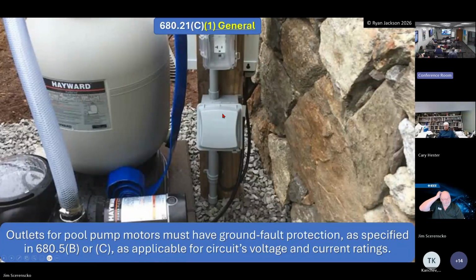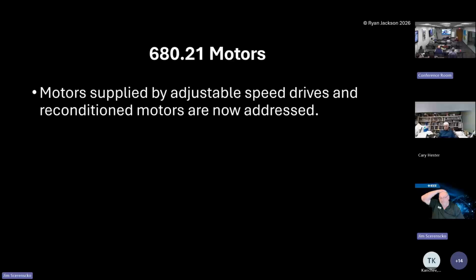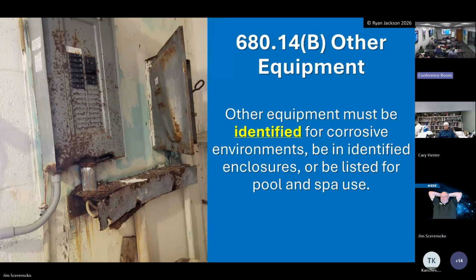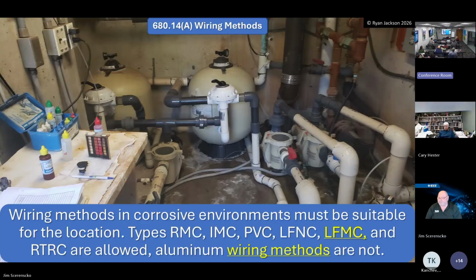I've a question. So going back to the panels, does that mean you said no aluminum? Can you go back one more slide? Where it says aluminum wiring method. So does that mean the feeder going to the panel has to be copper? No, the wiring method itself is the raceway. You needed an insulated equipment ground for pool equipment anyway, so you're not going to really find any kind of NM cable or SE cable, unless you're going to use copper, but typically it's going to be the wiring method itself.